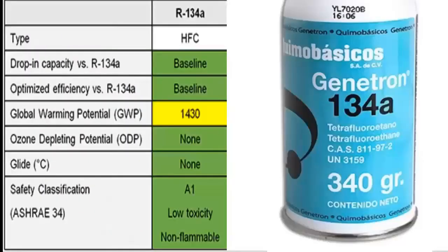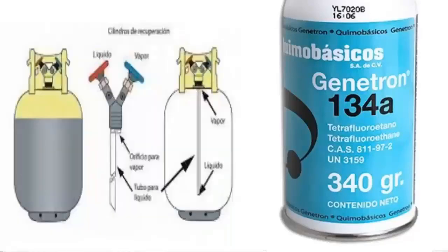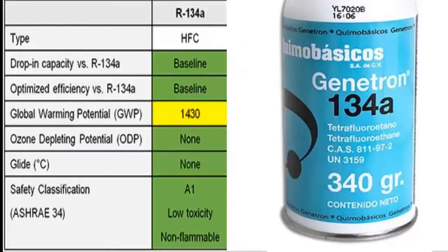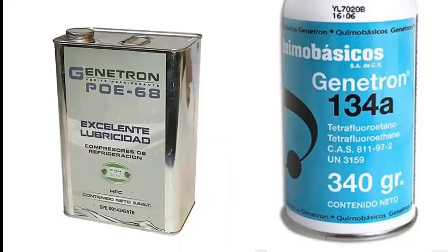11. Since R-134A is a refrigerant with no mixed components, it can be charged in a liquid or gaseous state. 12. It is not necessary to turn the container with coolant or use the liquid outlet. 13. As the evaporator temperature value begins to drop, the charge by weight becomes more important. 14. R-134A works with POE-type oil.